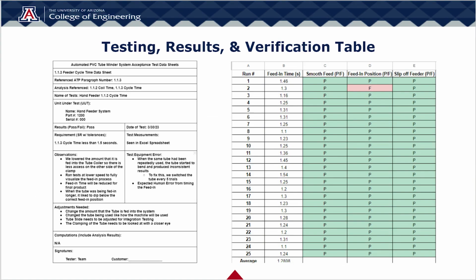As for the cycle time test that we performed, you can see that one fail on there. This is where we realized that we can't use the same tube for all of our trials, as it gets deformed over time. So what we did is we changed up the tube being used every 3 to 5 trials, and we passed from there on out.